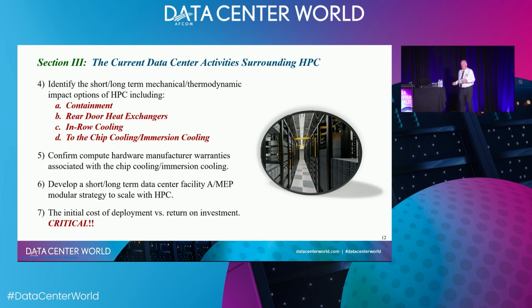Thermodynamics is key because it's going to show you how far can I go with airside load. 20 kW per cabinet? When does containment come into play? When do rear door heat exchangers come into play, when I start pushing over 25, 30 kilowatts per cabinet? I need rear door heat exchangers, in-row cooling, that can bring me up to the thresholds of 60 to 70 kilowatts per cabinet. And then, when I'm at 100, it's to the chip cooling.